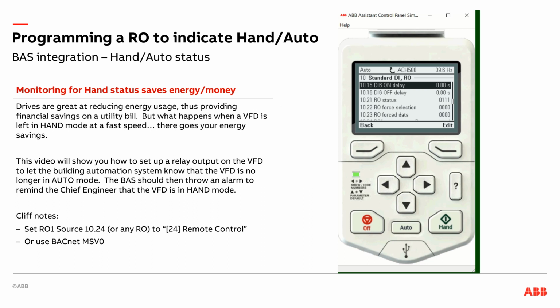A little pro tip on this one, if you're running a BACnet MSTP or any BACnet integration to the drive, there's actually a BACnet object for this. My favorite is using the multi-state value to see if I'm in hand, off, or auto. So if I do this over BACnet, it's actually free. I'm not even running that wire. So if you just noticed it got a little quieter, I just shut the demo off in the background.